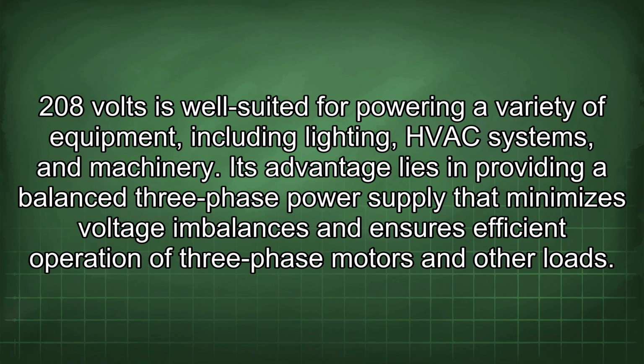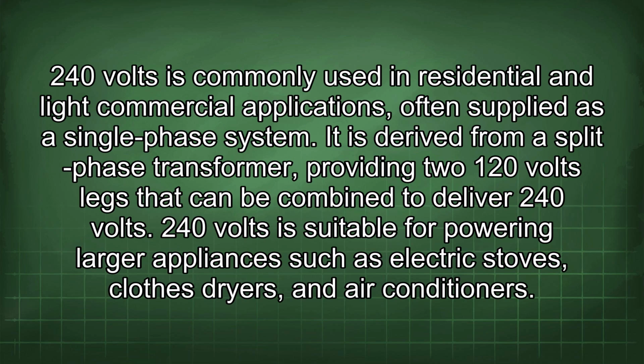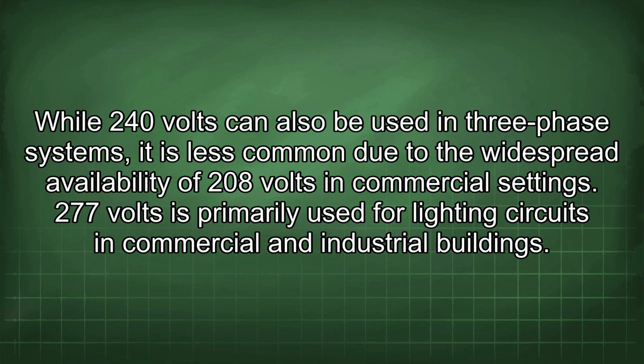208 volts is well suited for powering a variety of equipment, including lighting, HVAC systems, and machinery. Its advantage lies in providing a balanced three-phase power supply that minimizes voltage imbalances and ensures efficient operation of three-phase motors and other loads. 240 volts is commonly used in residential and light commercial applications, often supplied as a single-phase system. It is derived from a split-phase transformer, providing two 120 volts legs that can be combined to deliver 240 volts. 240 volts is suitable for powering larger appliances such as electric stoves, clothes dryers, and air conditioners. While 240 volts can also be used in three-phase systems, it is less common due to the widespread availability of 208 volts in commercial settings.